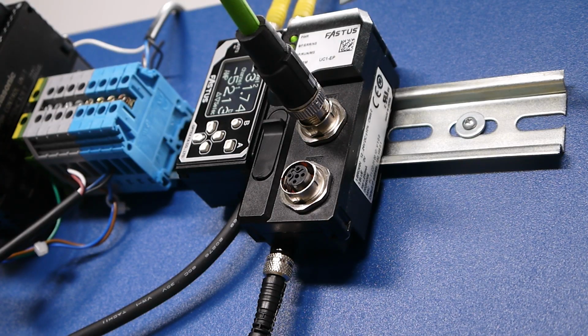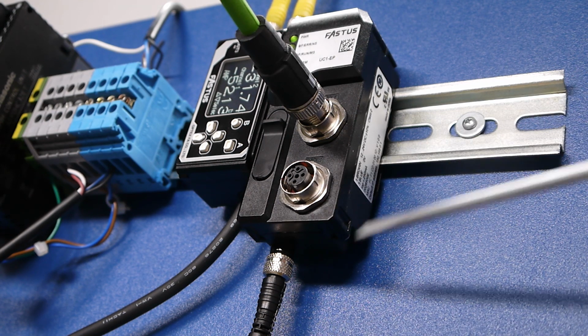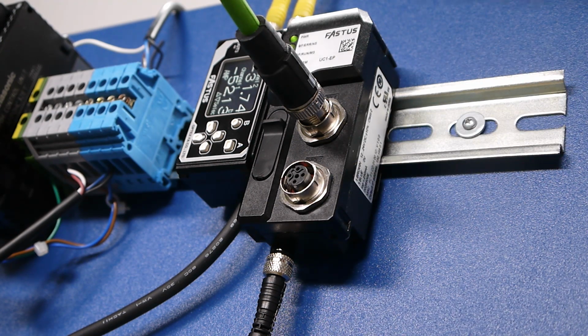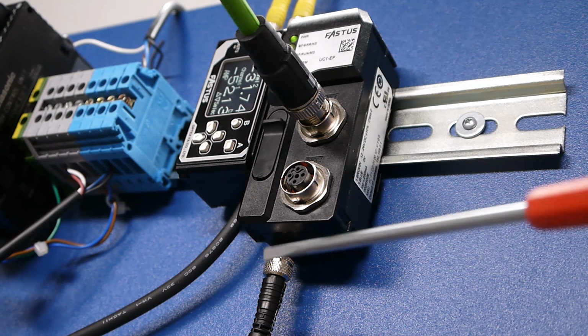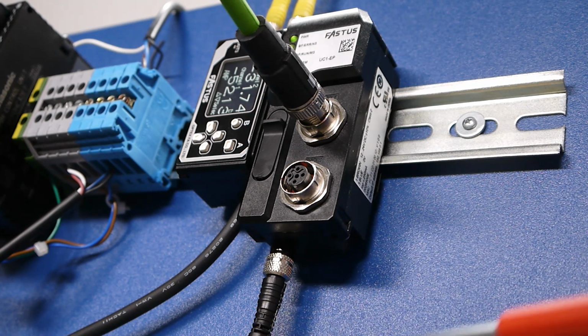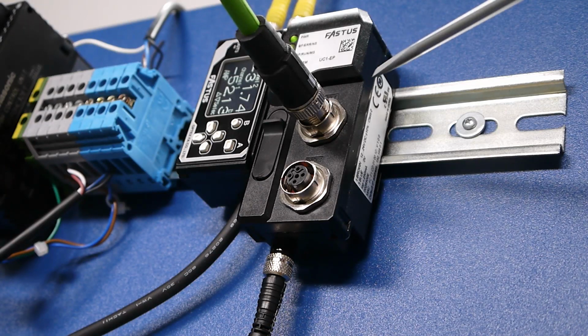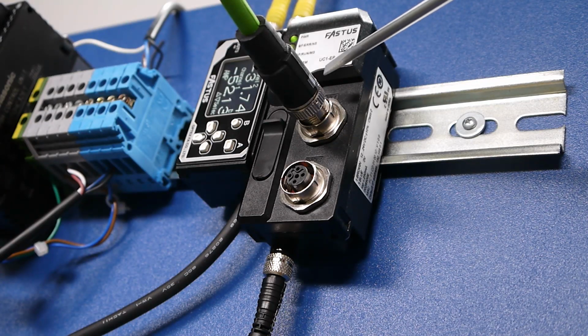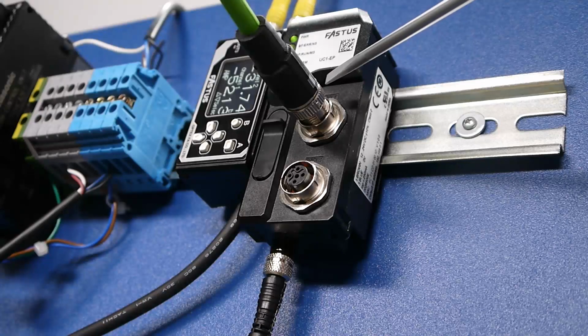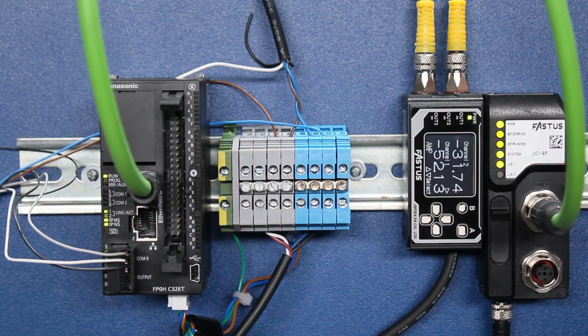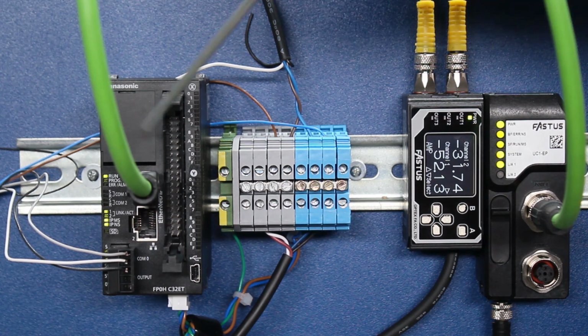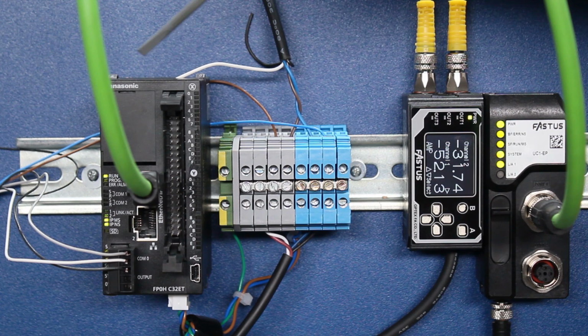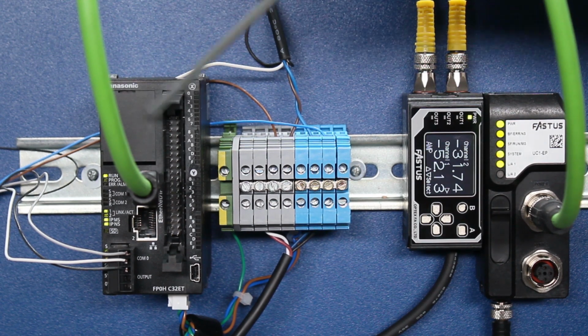So this is the UC1-EP communication unit, Ethernet IP communication unit. You apply power here. And this is where you connect your Ethernet connector to it. So it's an M12 5-pin cable going over to the Ethernet IP port on the PLC. In this case, we're using a Panasonic FP0H PLC.